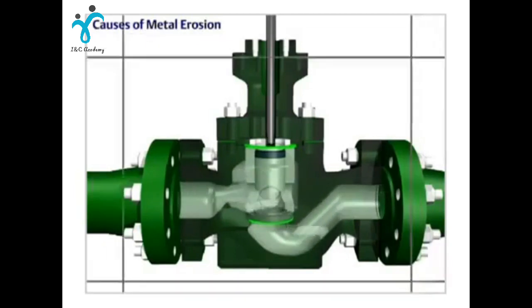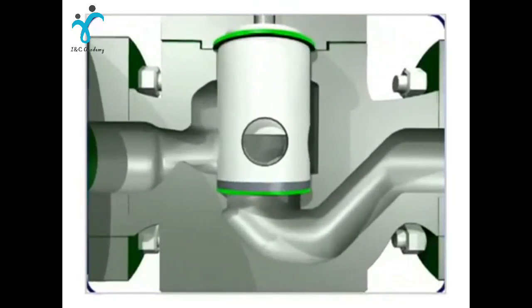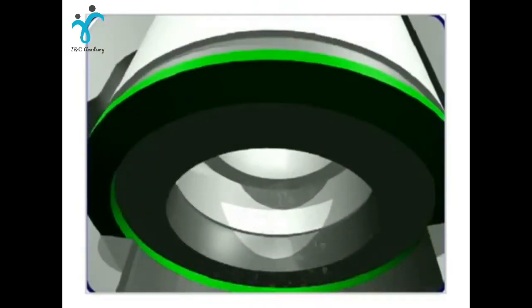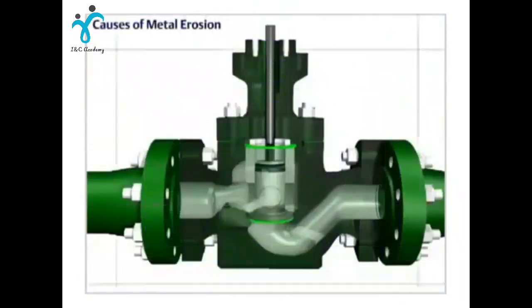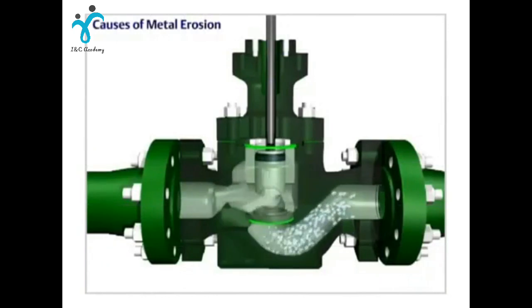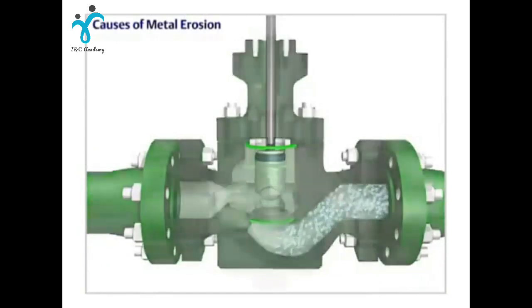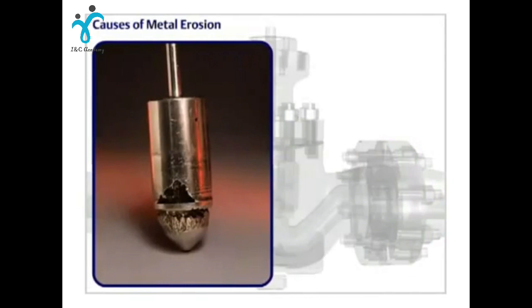Wherever there's a restriction in flow, the decrease in pressure can cause a fluid to reach its vapor point. Flashing occurs when the fluid vaporizes and remains a vapor. Metal erosion caused by flashing appears smooth and shiny.